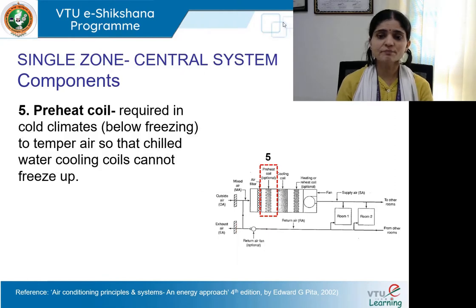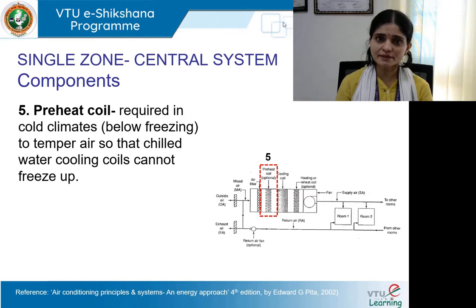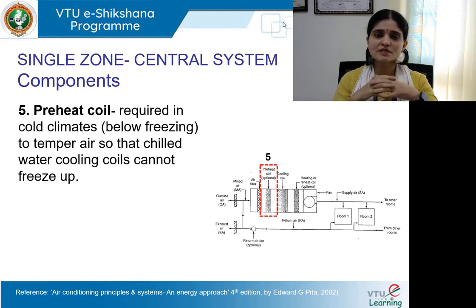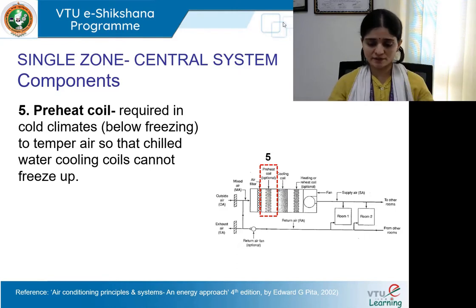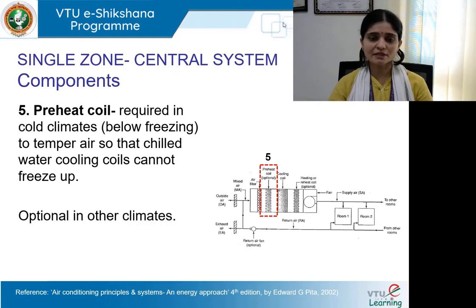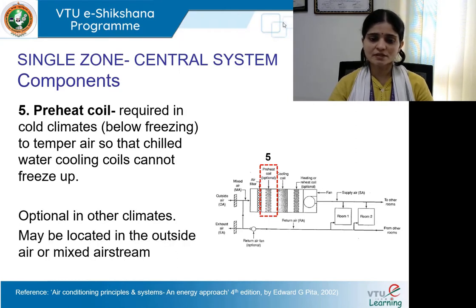Number five: the preheat coil. This is an essential requirement in colder climates — below freezing temperatures. It is used to temper the air so that the chilled water cooling coils do not freeze up. To avoid freezing of the cooling coils during extreme temperatures, we adopt the preheat coil. It is optional in other climates, not required in hotter climates, and may be located in the outside air or mixed air stream.